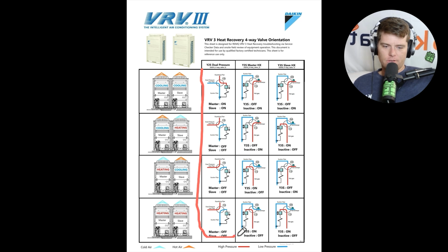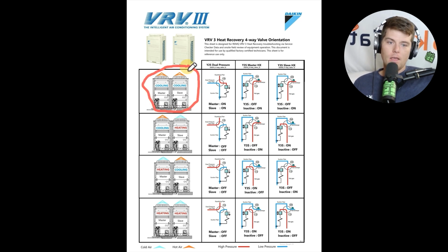Dual gas section, top to bottom. Okay, that's everything you need to know about dual gas. Here is the master main four-way valve for the outdoor heat exchanger. Here's the sub outdoor heat exchanger main four-way valve. Why is this important?